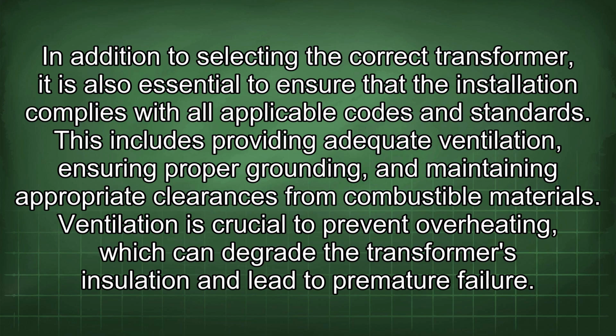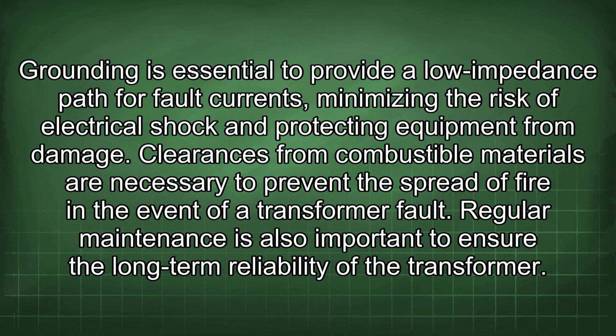This includes providing adequate ventilation, ensuring proper grounding, and maintaining appropriate clearances from combustible materials. Ventilation is crucial to prevent overheating, which can degrade the transformer's insulation and lead to premature failure. Grounding is essential to provide a low impedance path for fault currents, minimizing the risk of electrical shock and protecting equipment from damage. Clearances from combustible materials are necessary to prevent the spread of fire in the event of a transformer fault.